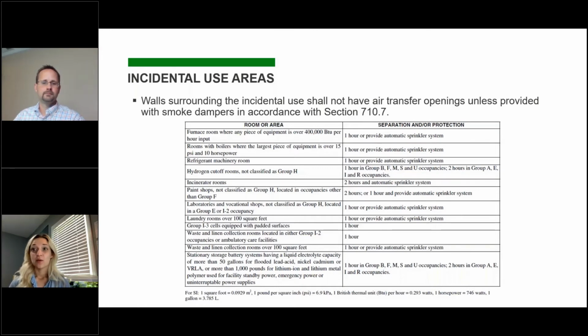What's really important to note about this table, which I think is frequently missed right off the bat, is that many of the requirements in the separation and/or protection column call out providing either a 1 hour fire rating or an automatic sprinkler system. And in most cases, especially in healthcare occupancies, the building is likely already provided with an automatic sprinkler system. But that doesn't necessarily mean we don't have to provide anything. There's a footnote to this table that clarifies that if you opt for the automatic sprinkler system option, then you need to provide a smoke partition around that room and protect it as necessary depending on the application.